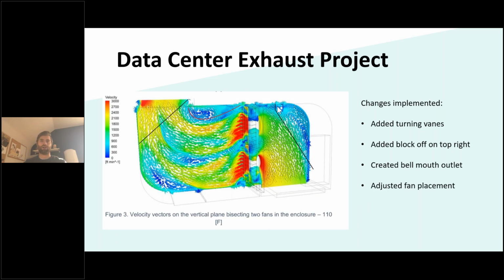So we added a block off on the intake side. We added a different style of turning vanes within the turn here, a bit of a block off at the top, and then a bell mouth outlet on the exit. In addition to that, we also offset the bottom fan. It's a 4-fan array here, and we offset the bottom to induce more of that curve of the airflow through there.